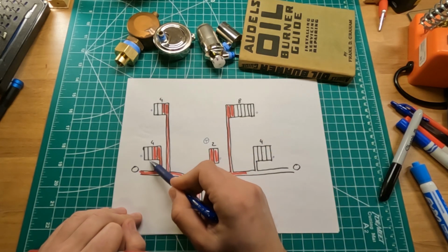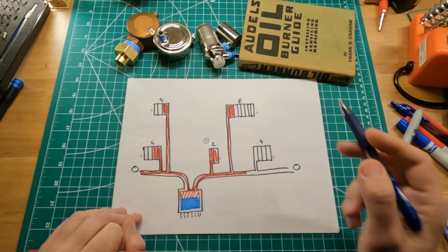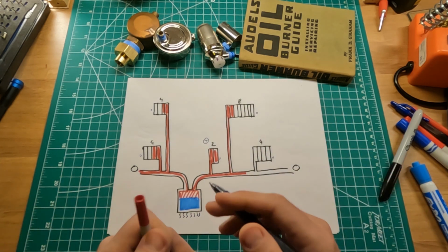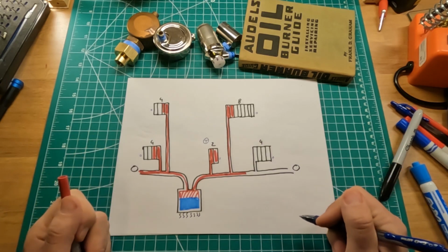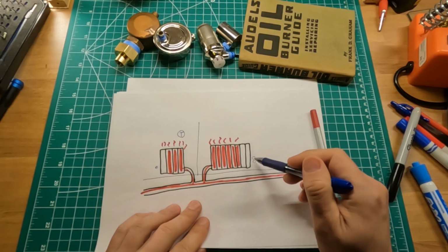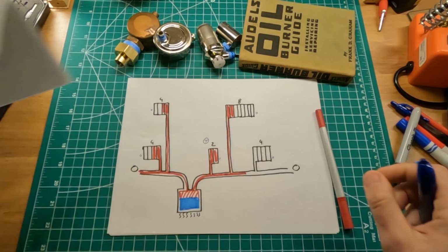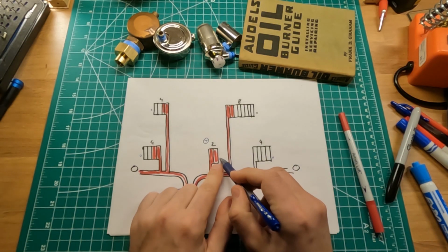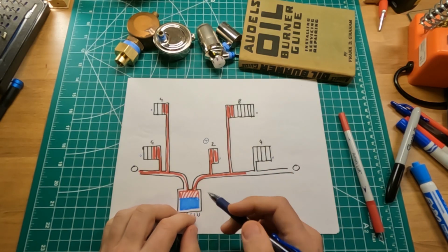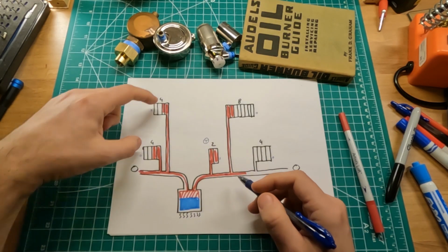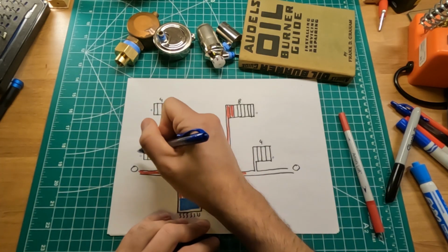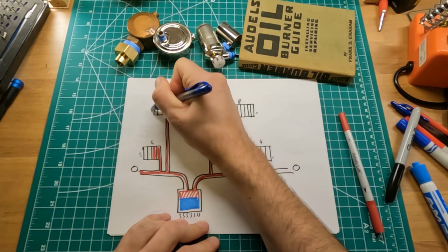This radiator, only half of the radiator gets filled up, and this radiator, only half the radiator gets filled up. So let's say we have an issue. How do we solve this issue? Once again, we start working with the size of the air vent openings. If this small little vent with this low opening allows us to fill up 2 sections, then if you want all the radiators to completely fill up, we will have to increase this venting rate. So let's say double the dots.